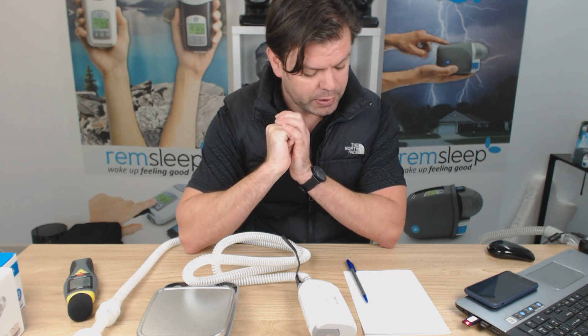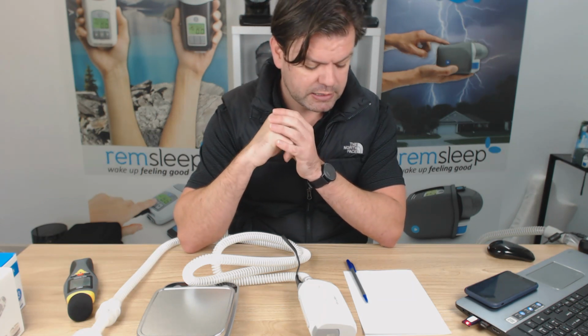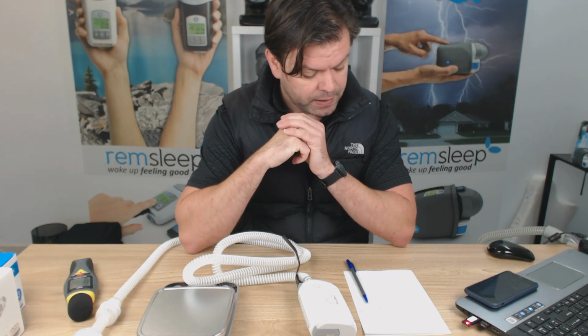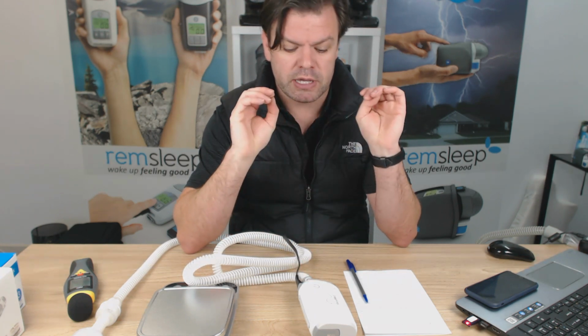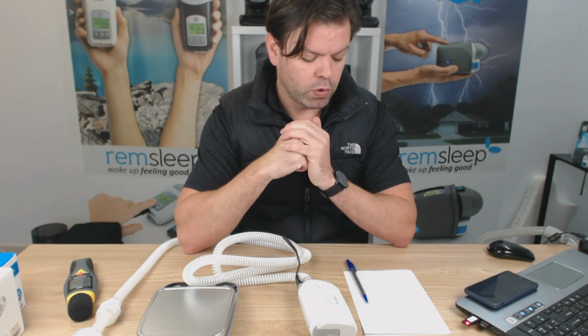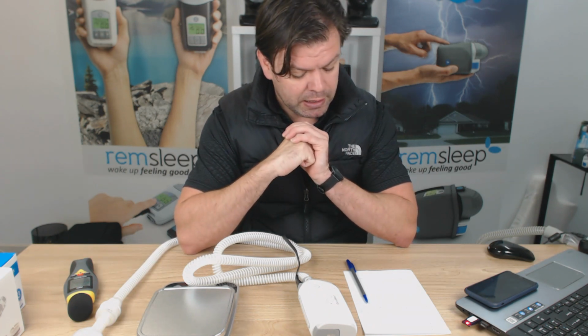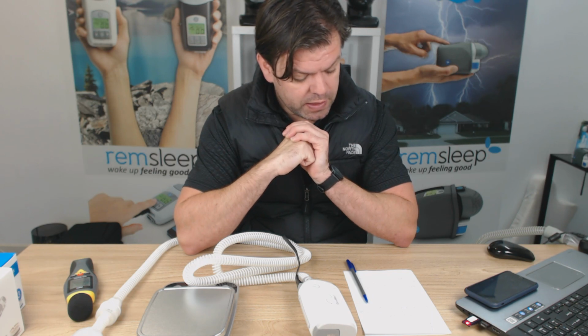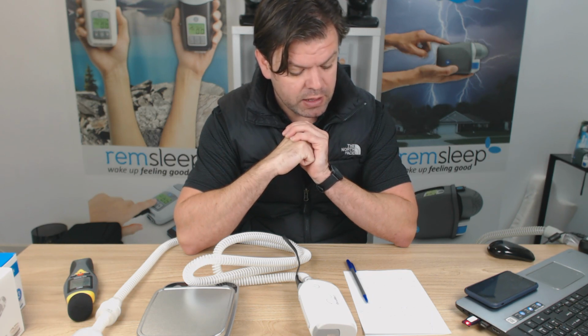It has an automatic ramp, which can detect sleep onset. So what that means is the machine itself will stay very nice and low in pressure until you fall asleep. Once you've fallen asleep, the machine will then adjust higher to control your sleep apnea. You can run it in CPAP mode or auto mode, but you can't just get a fixed pressure machine. You can only really get the automatic one and then run it in either fixed pressure or auto mode, with probably 99% of people running it in automatic mode. They're the sort of main features that you have there.